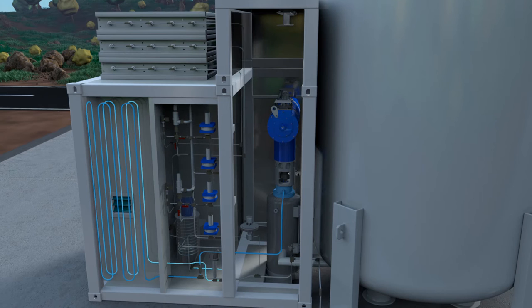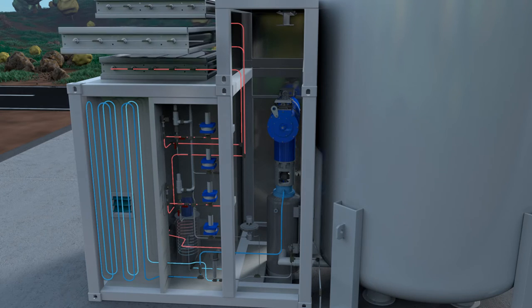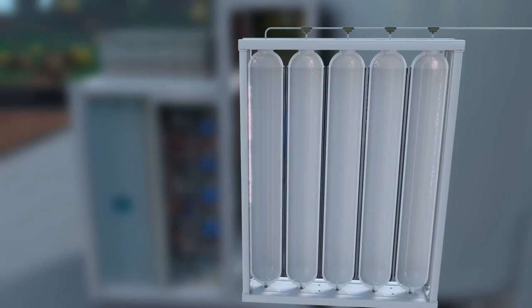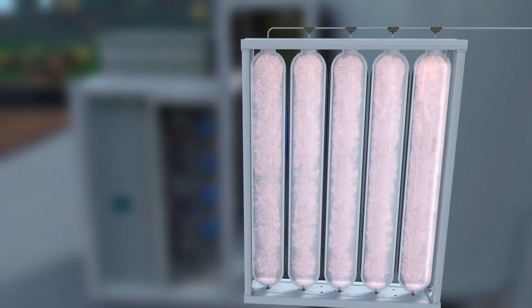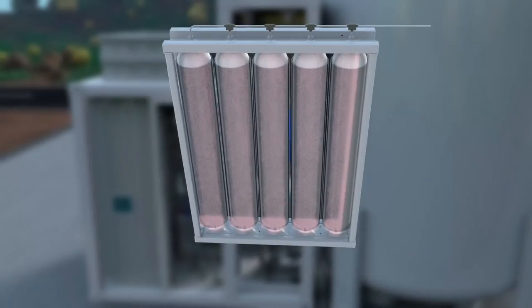The compressed hydrogen is filled into the storage tanks, where the gaseous hydrogen is temporarily stored at a pressure of 1000 bar. The combination of the Cryo Pump and the storage tanks enables fast fueling, even of several vehicles in a row.